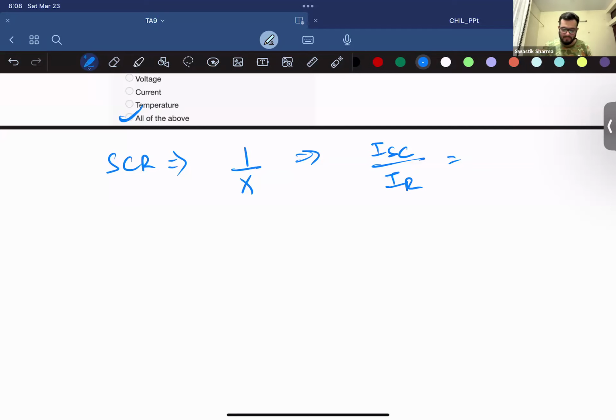So what usually happens is as the impedance increases, the value of X will increase. So your short circuit ratio will be less. If the impedance of the system is more, the short circuit current will be less, right? So even when some fault happens in the system, what happens? The relay works on the principle of measuring this short circuit current. If the short circuit current is low, how will the relay measure it? So the sensitivity of the relay will decrease because the impedance of the system is more.